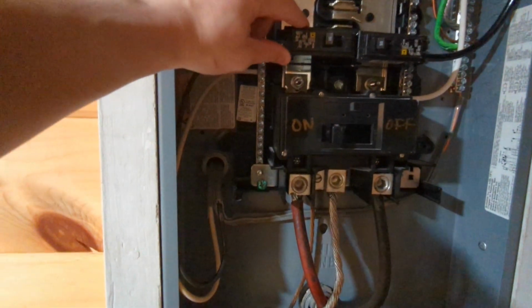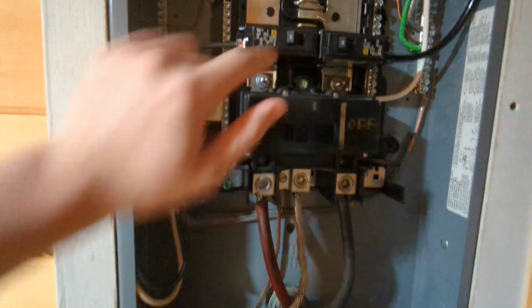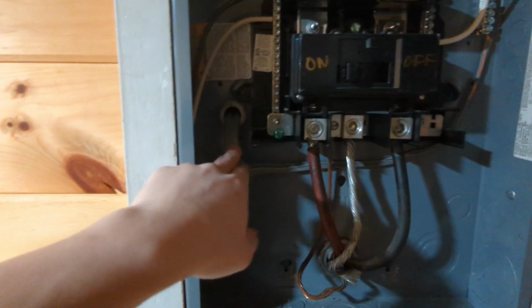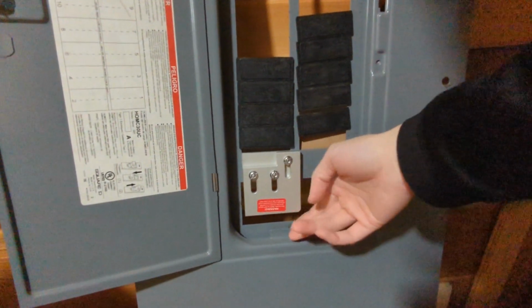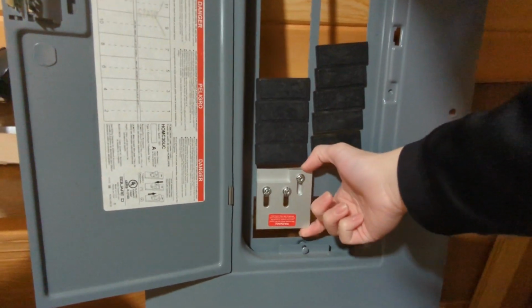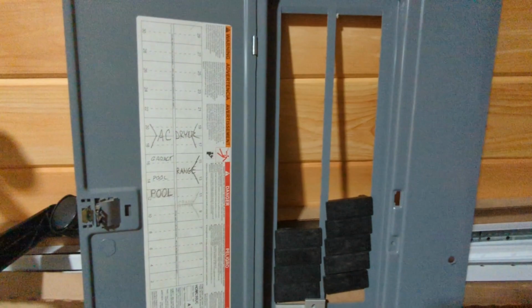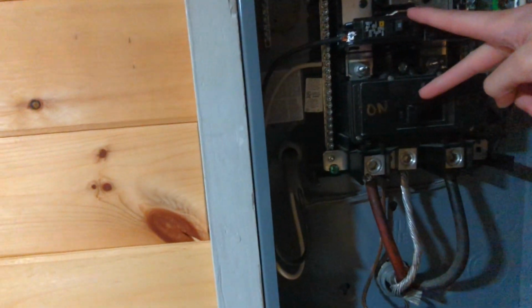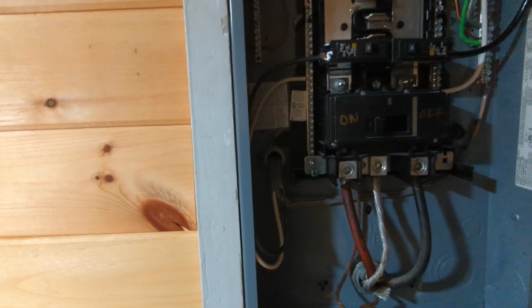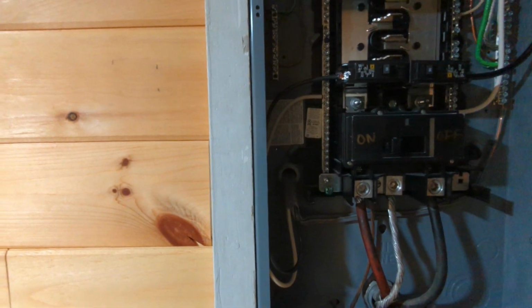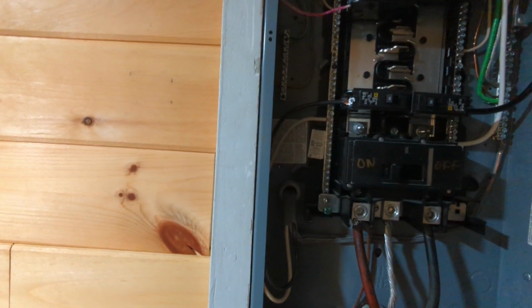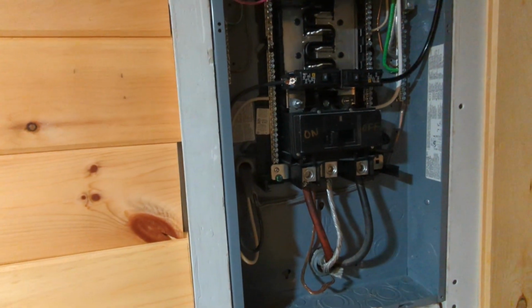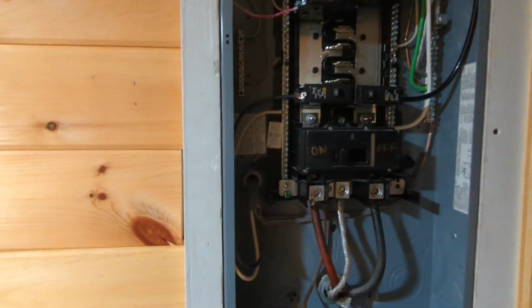This breaker right here is a 30 amp breaker. This is an outdoor UFB wire. The lockout plate is actually right here. See, that's set in place in this position between these 2 breakers. My inverter generator does 30 amps with the TT30P RV receptacle, 3,000 watts on propane running watts, and then the gasoline running watts is 3,200.